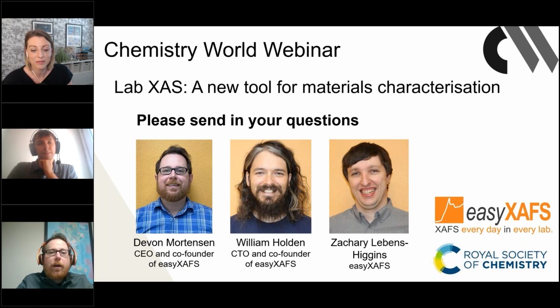Yeah, so we're able to recover synchrotron level resolution. That's all determined by the crystal analyzer itself. The analyzer that we're using, the spherically bent crystal, I'll try not to get too into the details, but this is the same type of optic that is used in different spectrometers at the synchrotron as well, like if you were doing RIXS or HERFD or something. So it's a synchrotron quality optic. That's what we're using in the laboratory instrumentation. And with that, we're able to get the same energy resolution.